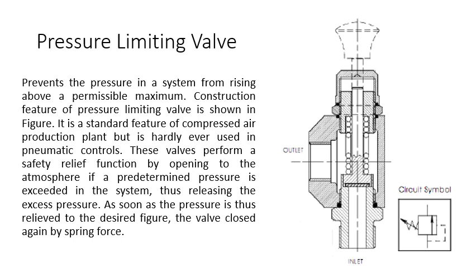The valve releases pressurized air to the atmosphere if the pressure reaches the predetermined level. This releases the excess pressure to the atmosphere; as soon as pressure is thus relieved to the desired figure, the valve is closed again by spring force. If the pressure increases above the set value, it releases to the atmosphere, and when it reaches the required set pressure, it automatically closes the opening. For this reason, it is called a pressure limiting valve — it will safeguard the pneumatic system.